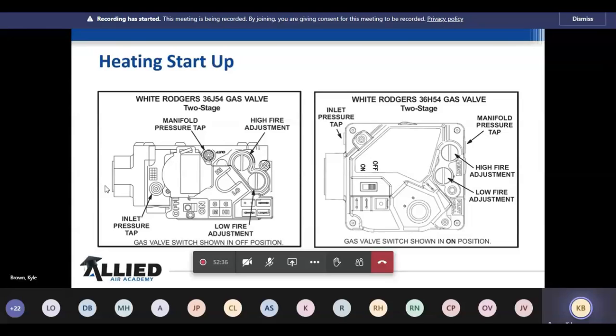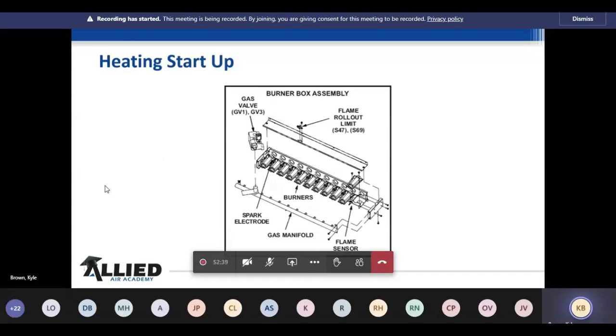So you want to check the gas pressure. One of the most important things I can tell you to check is, again, we talked about these units being on the back end of a truck, going down the road, shaking, bumping. You don't know what's going to happen. Let's take a good long look at these burners and make sure they didn't get moved. Just the slightest impingement on that vestibule panel, and you're going to have this flame rollout switch kick out on you. So before we start everything up on the heat, let's always take a look and make sure none of these burners got moved around during transit.